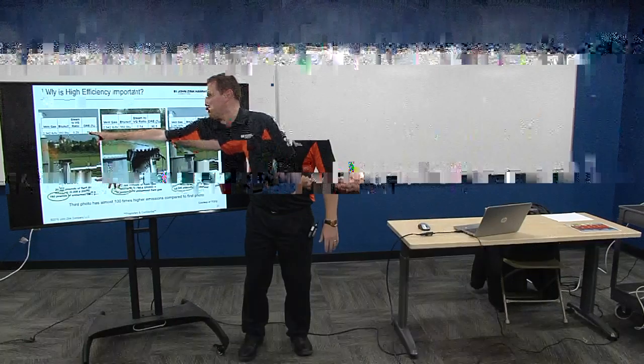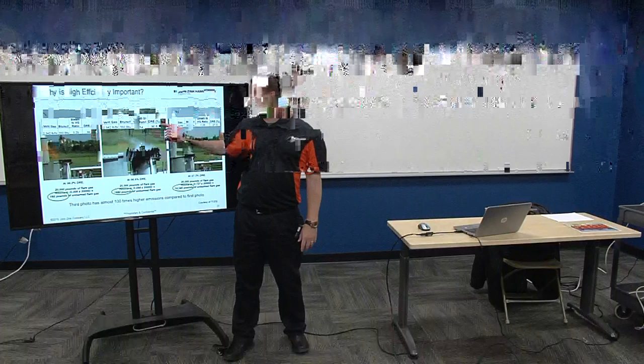Let's see, steam to vent gas ratio. If you remember, that steam was at a 0.3 with a 99% destruction efficiency. This steam to vent gas ratio went to 0.5, so we just increased it a little bit, but it dropped all the way to 90, right? But you see the flame's starting to go away. You see a little bit of fire out there.